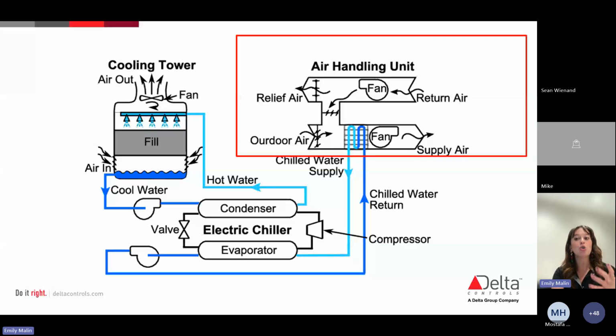When your room temperature is too warm, the control system is yet again going to send a signal to open that valve. It's going to say, hey, we need more cold water to be flowing into our air handling unit. Again, this happens by sending a signal to an actuator. The fan in the air handling unit is then going to blow air across that chilled water coil, which is actually what is chilling the air. So that's how you're actually going to get that cool temperature inside of your zone.